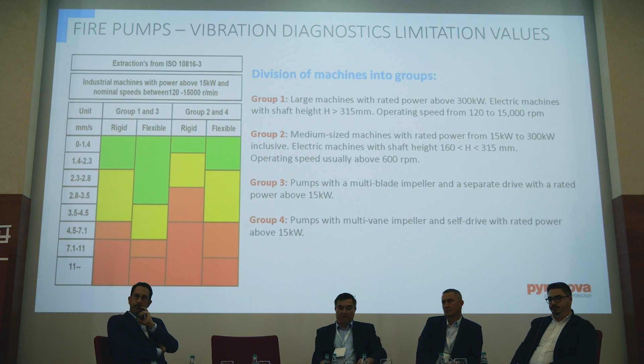The difference between rigid and flexible is the mounting. The machinery or pump is mounted to the ground. In our case, for diesel pumps, we usually mount them on rubber pads, which is a flexible mounting, and it helps offset the vibrations.